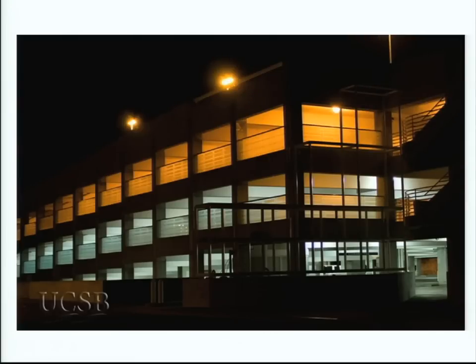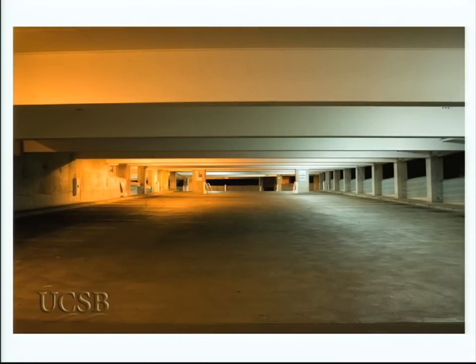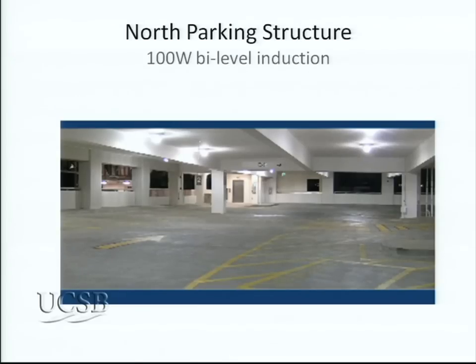This is the North Parking Structure during construction. You can see the new induction lights with higher CRI alongside the HPS fixtures — the picture speaks for itself. Side by side you can see the HPS environment and the clean, bright induction environment. People came in afterward and wanted to know if we had painted or cleaned the structure. It was so bright they couldn't believe it was the same place.